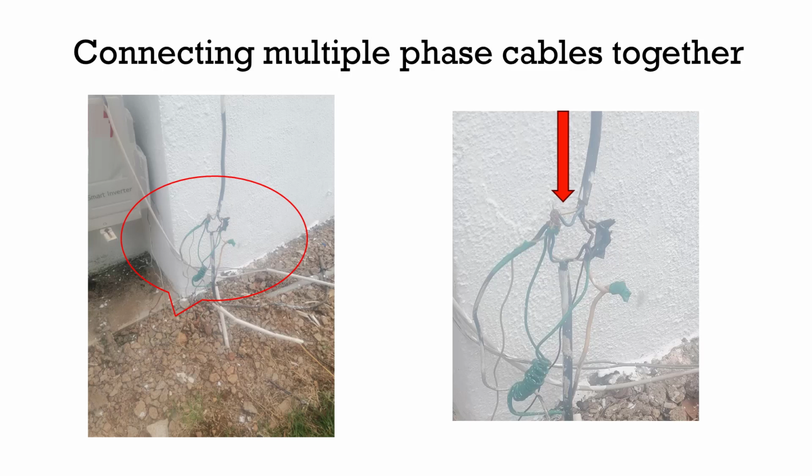So when we brought out a new junction box to reconnect this particular cable wiring, and because the cables that were going to the other buildings were only about two-phase and neutral, we now isolated one of these phases. Let's say we isolated the yellow phase and used only the blue phase and the brown phase and the black to supply the other buildings. So you will see in the other image how we isolated it.